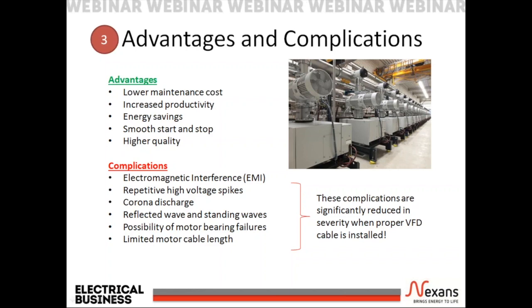Energy savings, running the motor at the optimal speed for the process rather than running at full speed or not at all. Smooth start and stop. By this, we mean slowly ramping the speed up or down. This reduces the mechanical stress on the system and creates a safer working environment. Higher quality. Accurate speed control means process optimization, leading to higher quality product. All of these advantages are key financial reasons to consider VFDs over single speed drives.